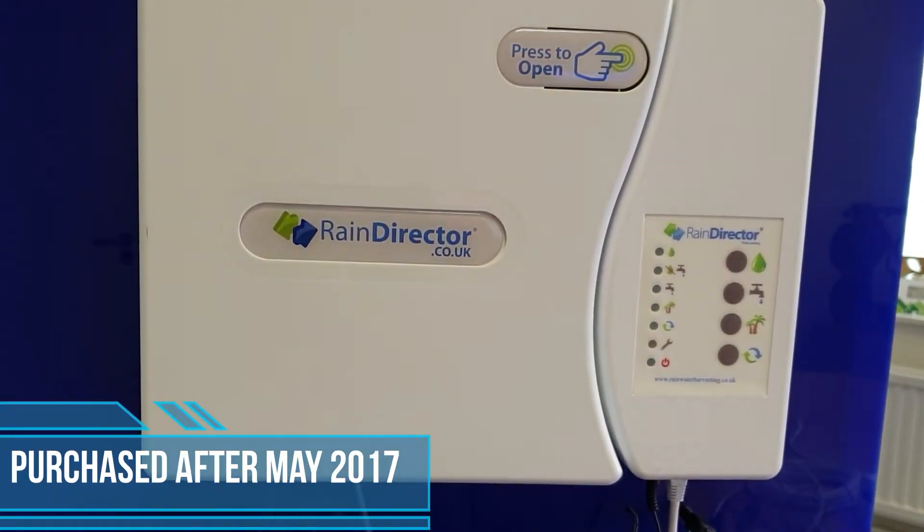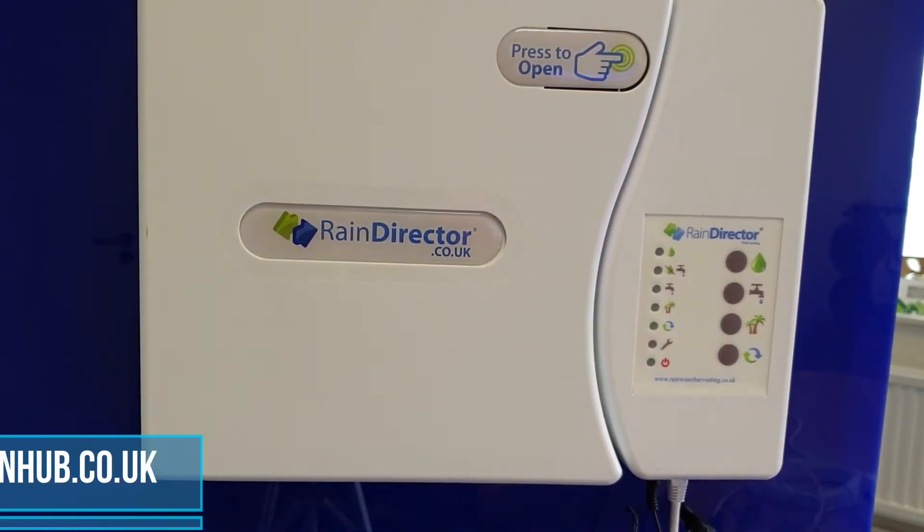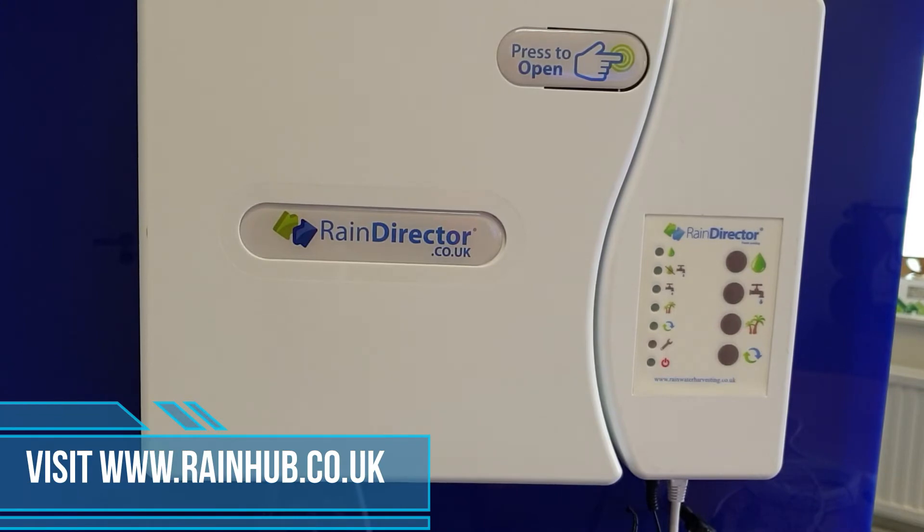Go up to the header tank and make sure your header tank is full of water. Then come back down and make sure your Cat5 is plugged into either of the ports underneath the rain director — it doesn't matter which port. Please make sure that the pump is turned on and there is water in the underground tank so the commission can take place.